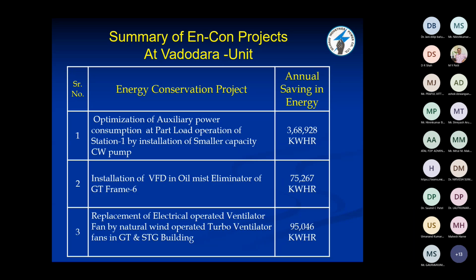Another project was the installation of VFD, that is variable frequency drive, in oil mist eliminator of GT frame 6 machine. Number 3, the replacement of electrically operated ventilator fan by natural wind operated turbo ventilator fan in GT and STG building. This is the energy saving in a year. The annual energy saving is 3,68,928 kilowatt hours. These are all figures that we can convert into rupees also. This is a saving that we have achieved by energy conservation.